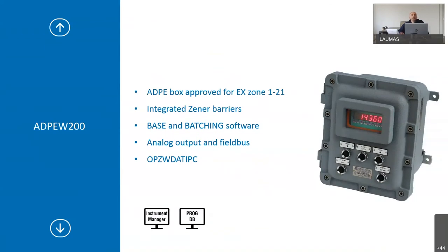ADPEW200 has the W200 indicator installed in an ADPE box approved for EX Zone 1-21, with two integrated Zener barriers — one for signals and one for power supply. Base and batching software can be installed as for the standard W200. Analog output and field buses are available. In this case only the PC record option is available.